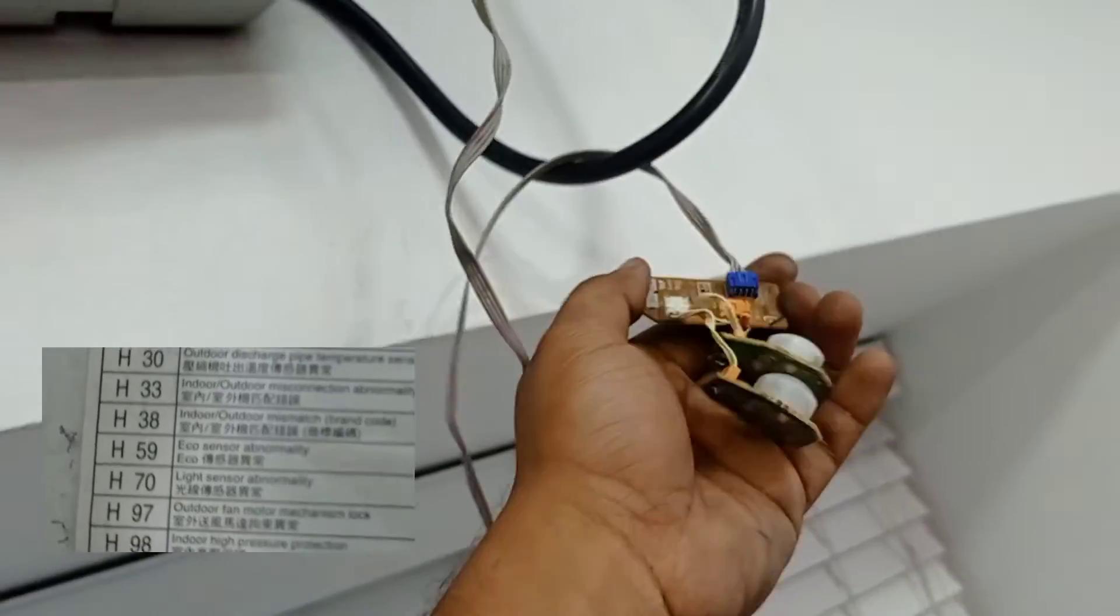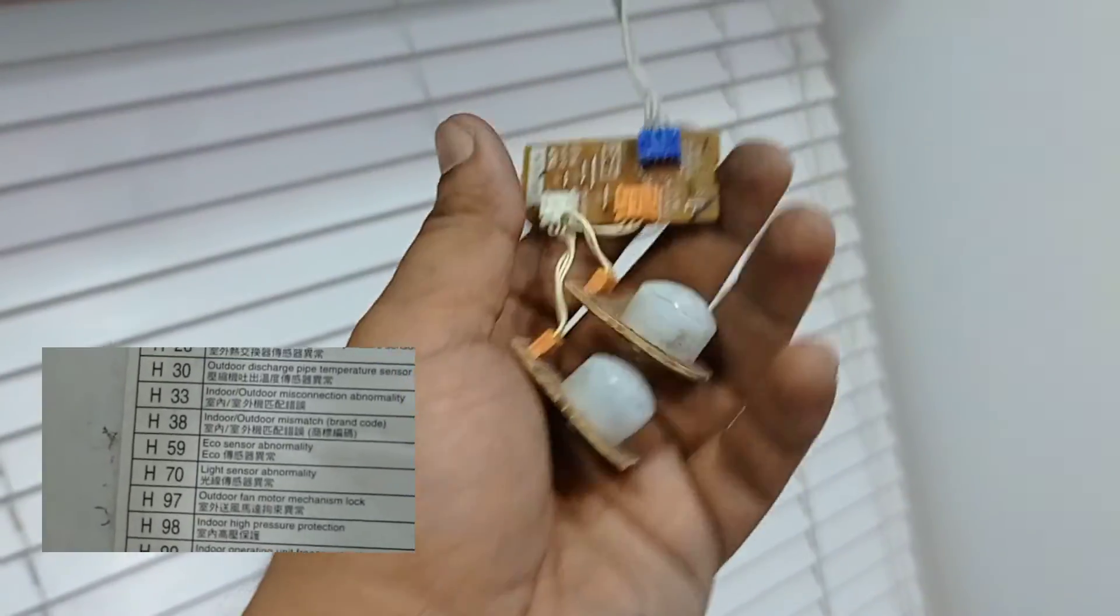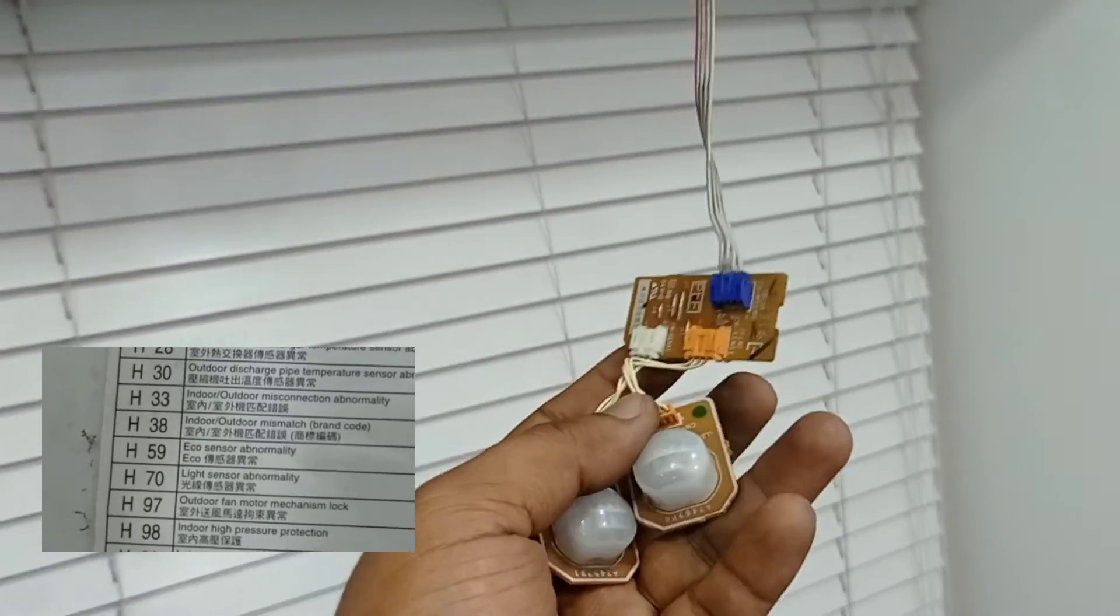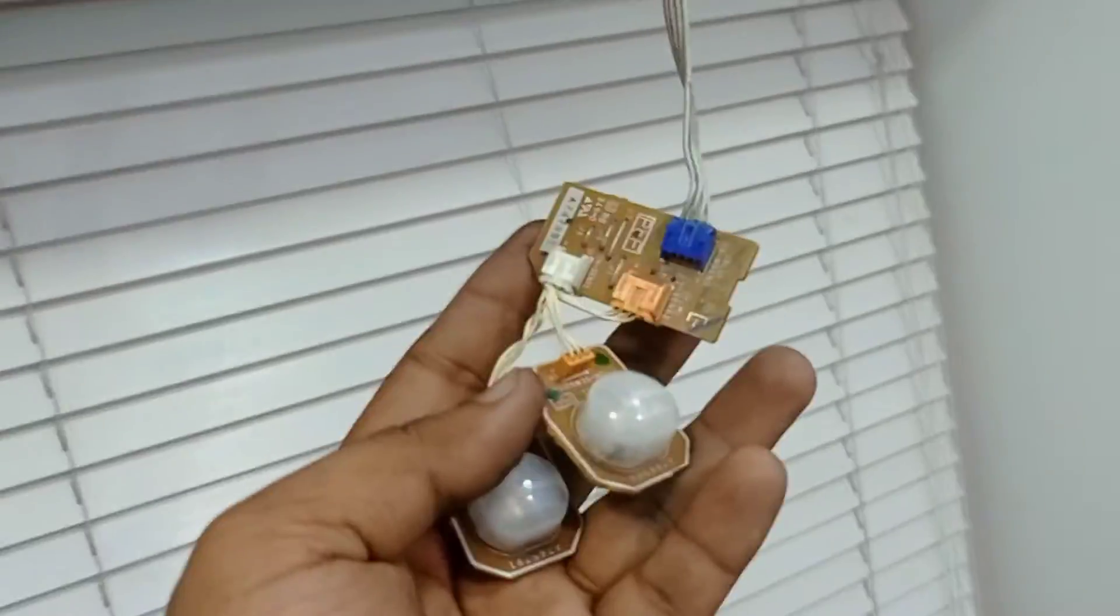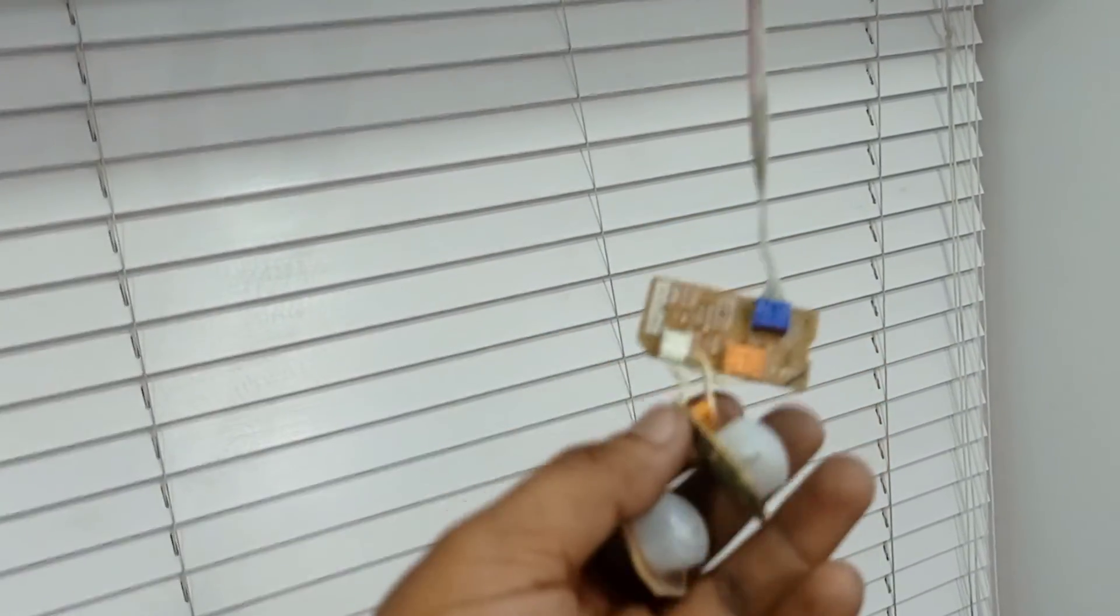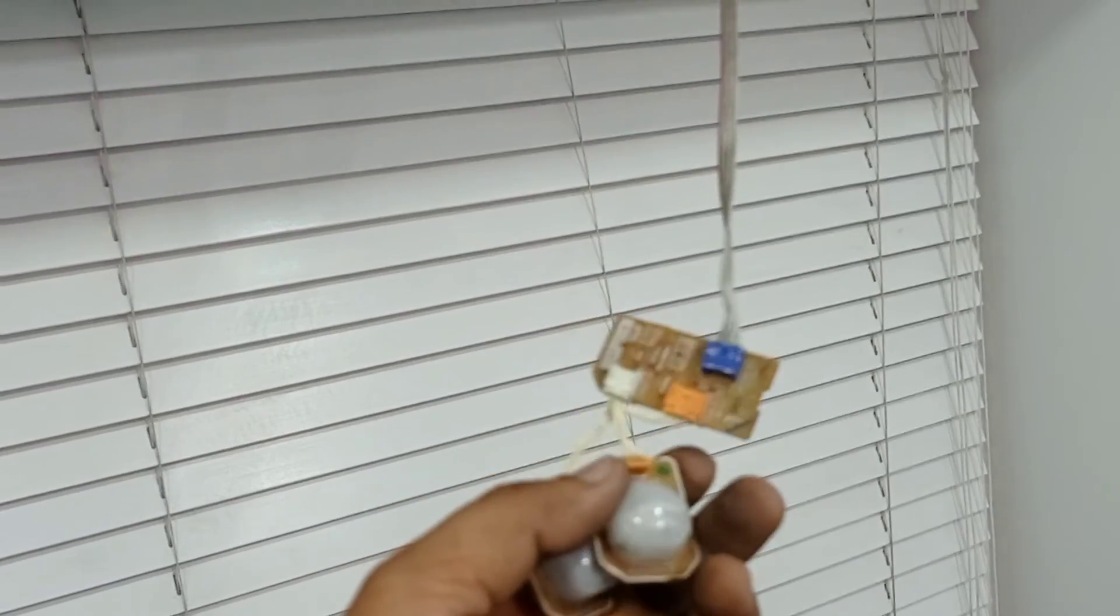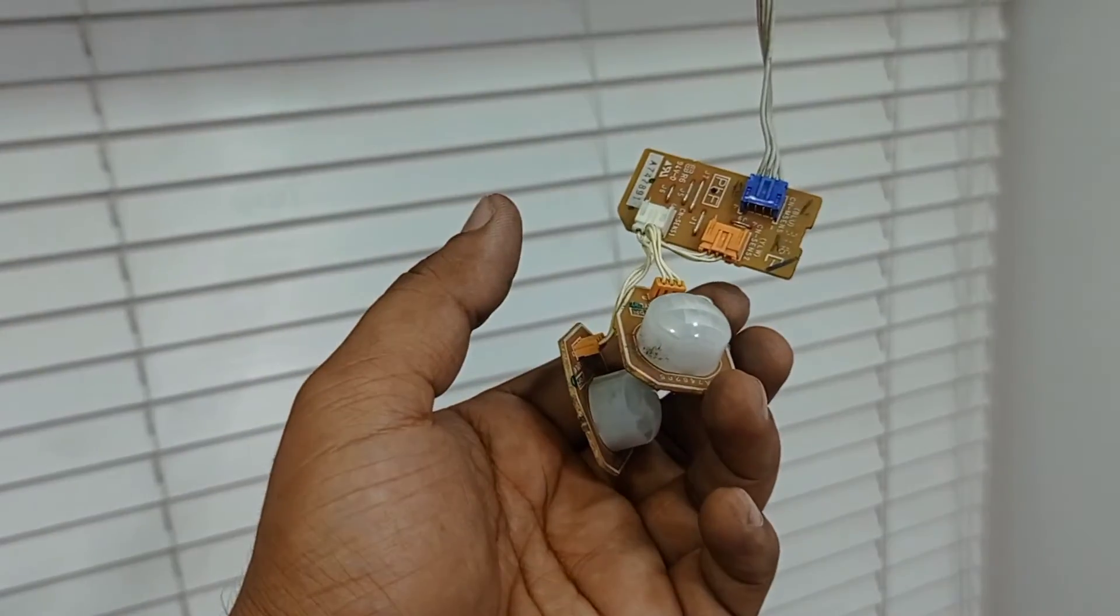This is H59 error. H59 means the ECO sensor is faulty. This is the ECO sensor - due to this fault, it's showing the error. We can't see any blinking in the indoor unit, but there is an error for this ECO sensor. Now I'm going to replace this ECO sensor and see if that resolves the issue.